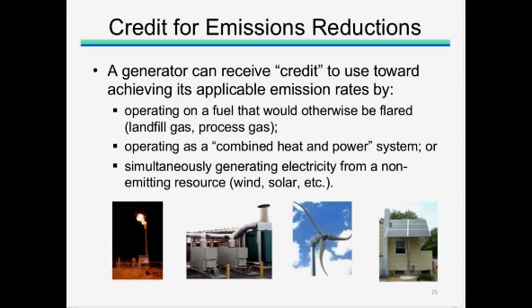To aid stationary generator owners in achieving their applicable emission rates, the model rule includes an optional section which would allow a generator to take credit for certain emission reductions. For example, if a stationary generator were to operate on a gas that would otherwise be flared, such as landfill gas, the emissions that would have been produced through the flaring could be deducted from the actual emissions of the generator. If a stationary generator were operating as a combined heat and power system where the thermal energy is used in addition to the electrical energy generated, the generator could then also receive a compliance credit against its actual emissions.